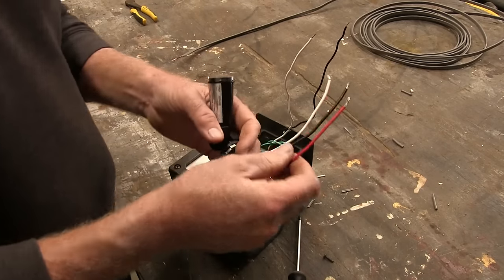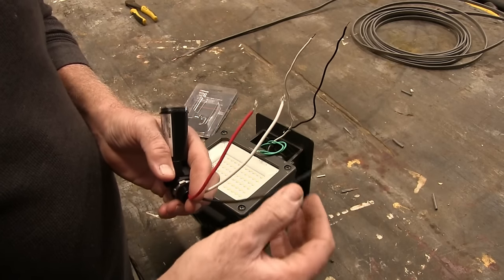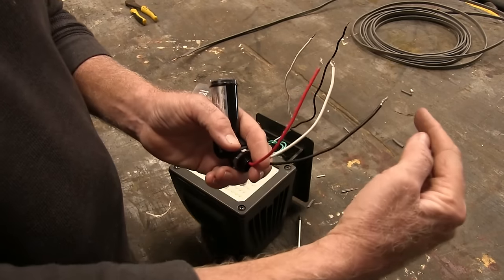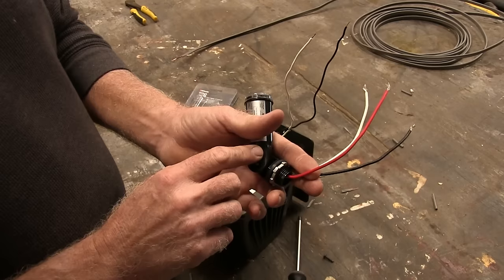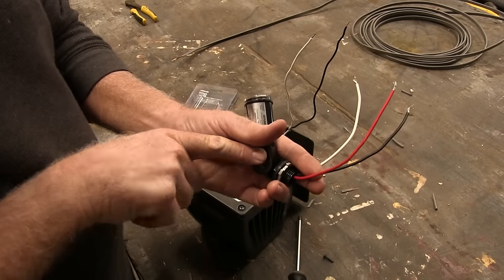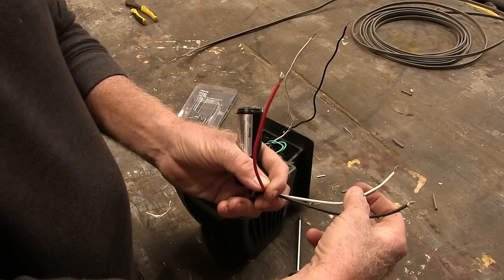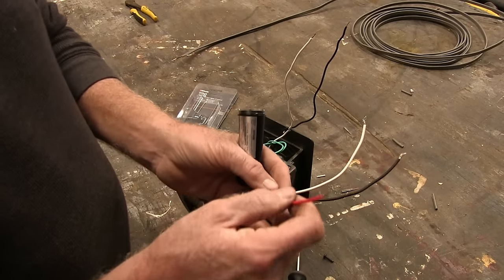In this photo cell you're going to have three wires: the black, which is hot (positive); the white, which is neutral; and then a red wire, which is also hot (positive). The difference is the hot coming in sends juice to the switch, and then the switch sends juice to the light through the red wire. So you've got power coming in through the black into the switch, and then back out through the red wire to your light.